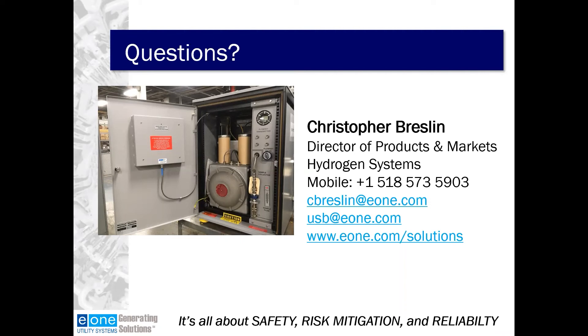Question: what size generators can use a GCMX? It really does not matter — any hydrogen-cooled generator can use it. We have them operating on nuclear units at 1,200 megawatts and on units down to 25 or 30 megawatts. If it's a hydrogen-cooled generator, the GCMX can actively monitor for hotspots.